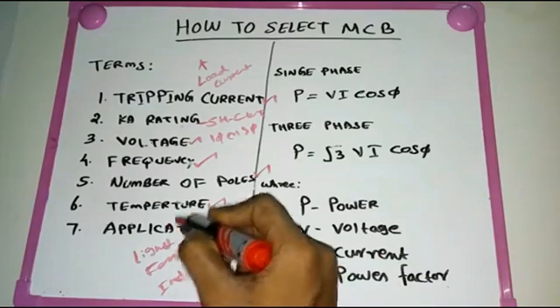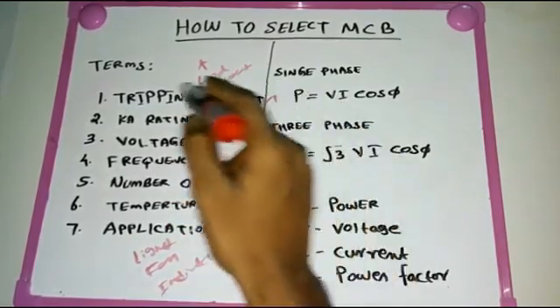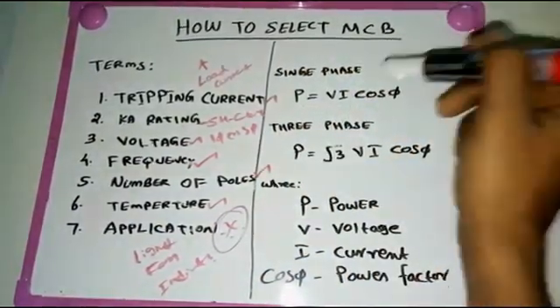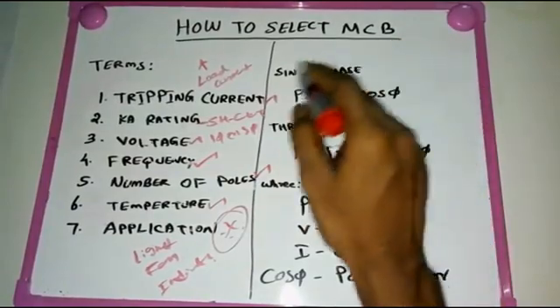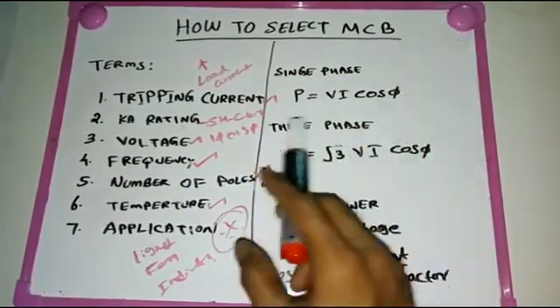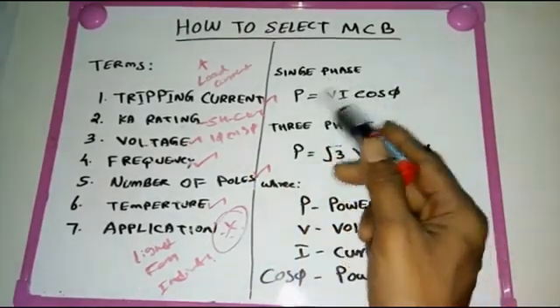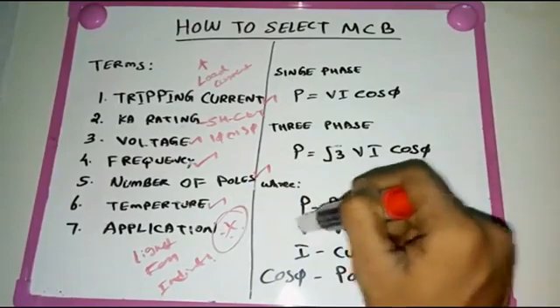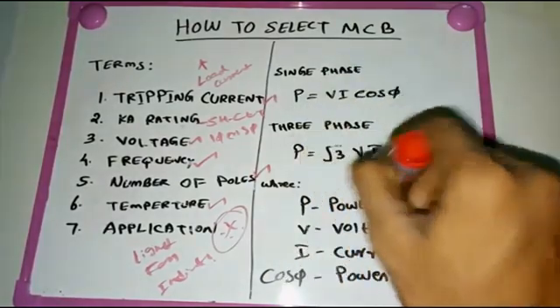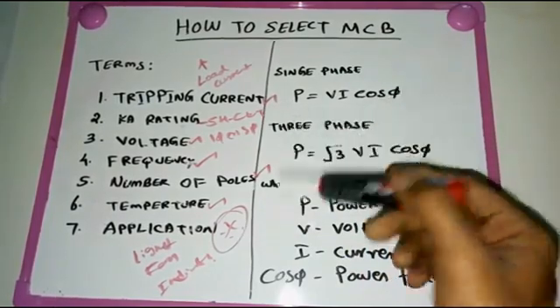So there are seven terms to consider when selecting an MCB. After identifying those, we use the power formula. For single phase: P = V × I × cos φ. For three phase: P = √3 × V × I × cos φ. Here P is power, V is voltage, I is current, and cos φ is the power factor.